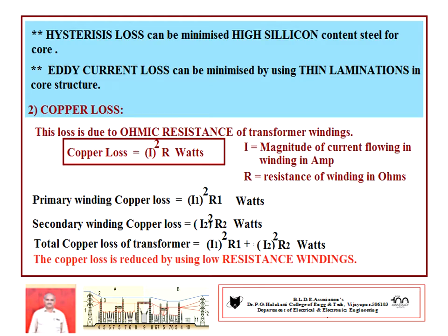And minimization techniques. The hysteresis loss can be minimized by using high silicon content steel for the core, and the eddy current loss can be minimized by using thin laminated structures of the core.